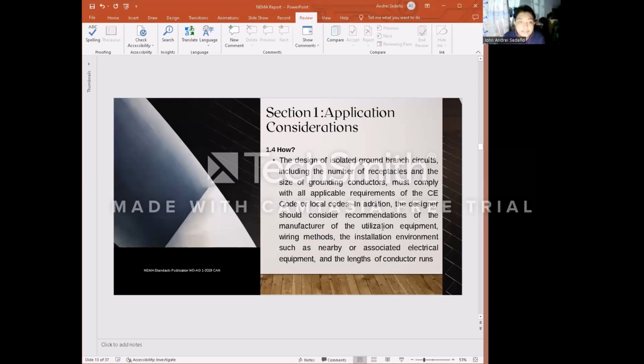Next is how. The design of isolated ground branch circuits, including the number of receptacles and the size of grounding conductors, must comply with all applicable requirements of the CE code or local codes. In addition, the designer should consider recommendations of the manufacturer of utilization equipment, wiring methods, the installation environment such as nearby or associated electrical equipment, and the length of the conductor runs.